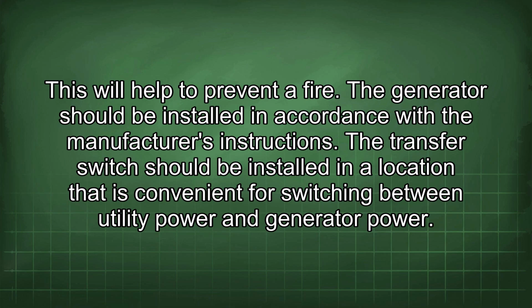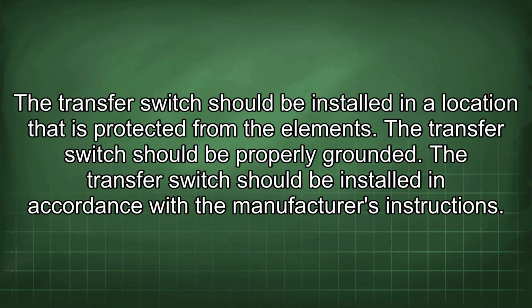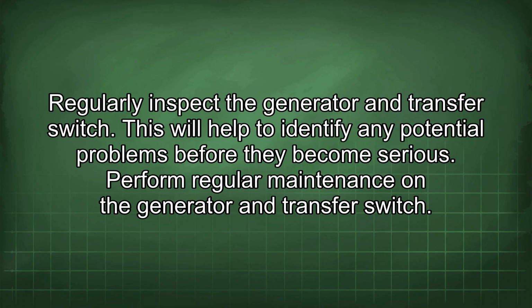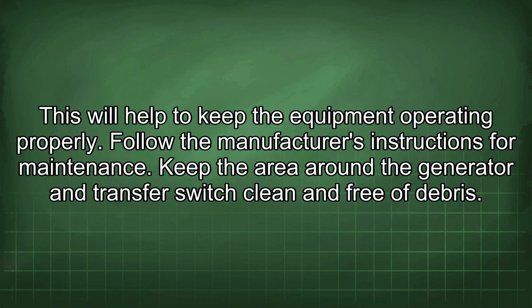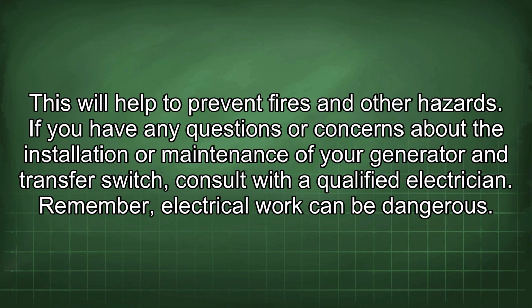The transfer switch should be installed in a location that is convenient for switching between utility power and generator power. The transfer switch should be installed in a location that is protected from the elements. The transfer switch should be properly grounded. The transfer switch should be installed in accordance with the manufacturer's instructions. Regularly inspect the generator and transfer switch. This will help to identify any potential problems before they become serious. Perform regular maintenance on the generator and transfer switch. This will help to keep the equipment operating properly. Follow the manufacturer's instructions for maintenance. Keep the area around the generator and transfer switch clean and free of debris. This will help to prevent fires and other hazards.